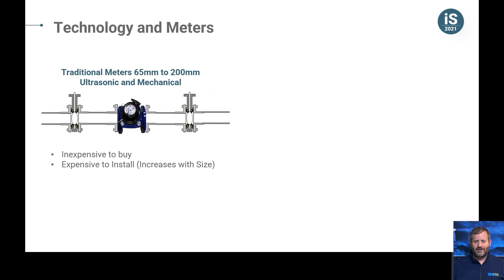I'd like to look at how technology is driving product evolution. I'm going to take three non-traditional products that are attached to the BMS, but many people overlook them. First, from a metering standpoint, we look at the traditional meters, ultrasonic and mechanical. They're very inexpensive to buy, but the issue is they're very expensive to install. With any type of flange meter over 65 mil, you need to be welding these large flanges and then mating them to the meter. You also have to have the meters prior to doing any on-site pipe installation or pipe testing or pressure testing.